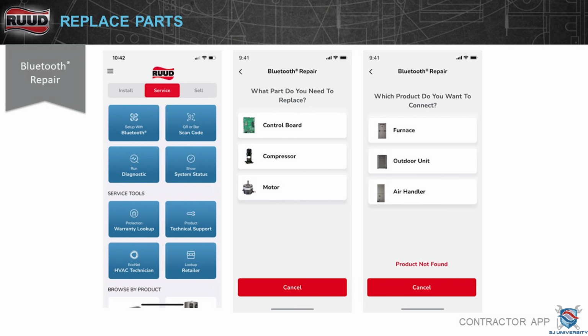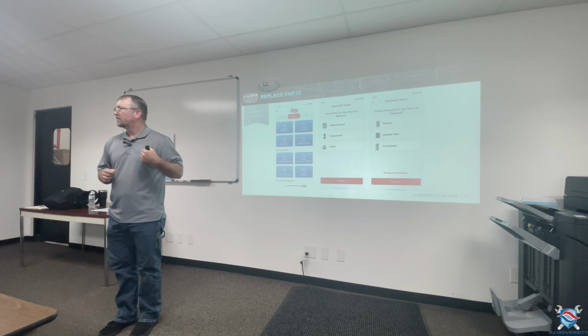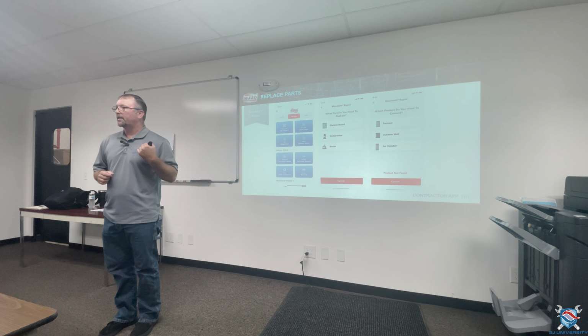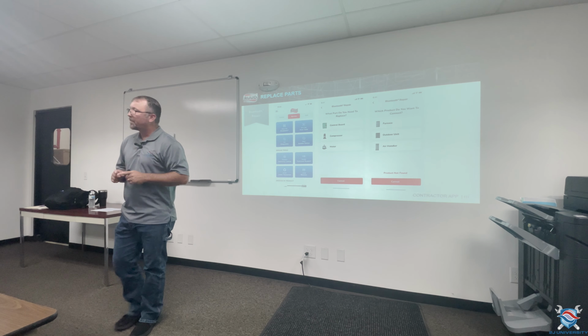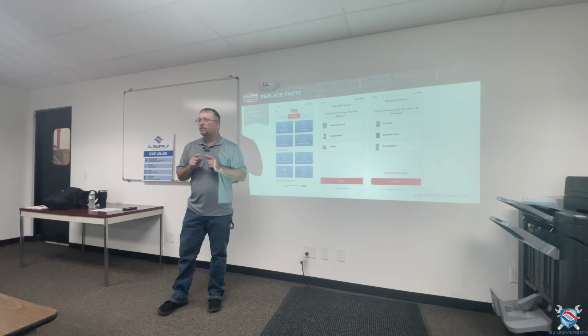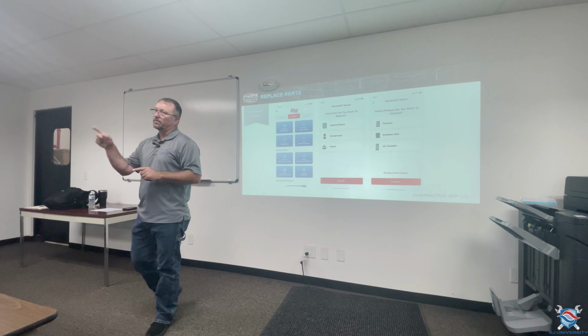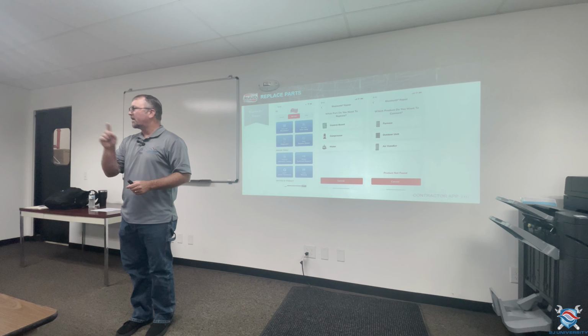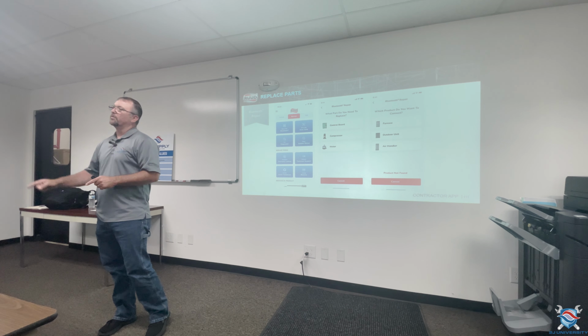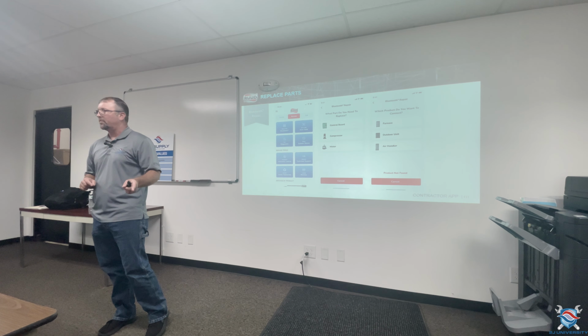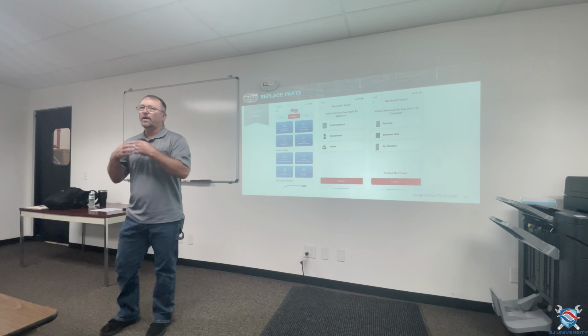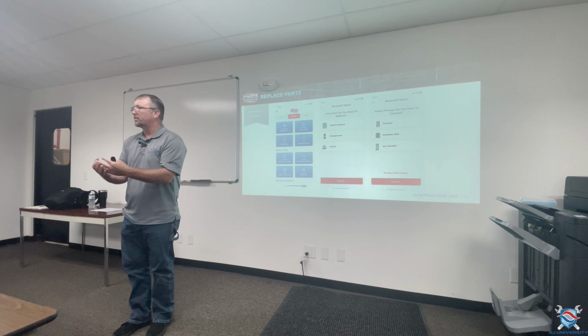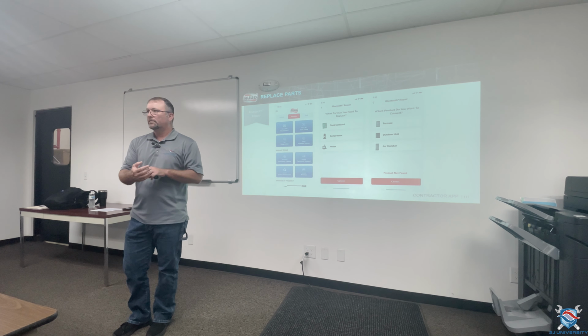If you are replacing a control board and it's hooked up to Econet, pull the Econet pin and disconnect the Econet from that control board. Because what will happen is it will send you into a tailspin in this big circle, because it's going to continuously try to find that Econet if it's plugged in. So it'll just tell you, set this up on the Econet. Well, you can't set it up with the Econet. You have to do the initial setup through the Contractor App, then plug in the Econet.